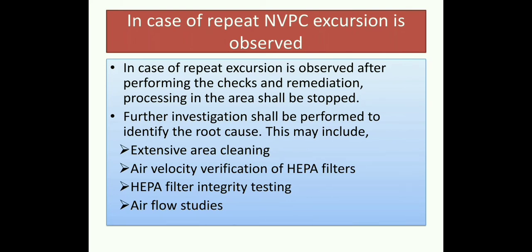Now we will see the action plan in case of repeat NVPC excursion. This is the case where initial remedial actions are not satisfactorily reducing or stopping the excursions and excursions are repeated. In case of a repeat excursion, processing in the area shall be stopped and further investigation shall be performed to identify the root cause. This may include extensive area cleaning, air velocity verification, and checking HEPA filters, as the root cause is often pertaining to the air coming into that area — including HEPA filter integrity.